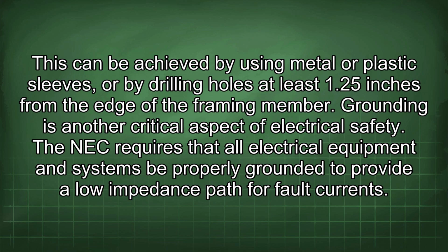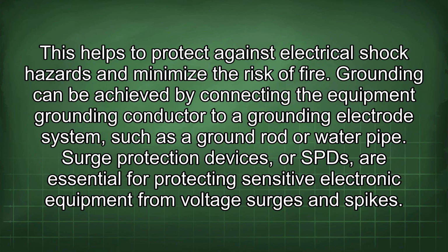Grounding is another critical aspect of electrical safety. The NEC requires that all electrical equipment and systems be properly grounded to provide a low impedance path for fault currents. This helps to protect against electrical shock hazards and minimize the risk of fire.